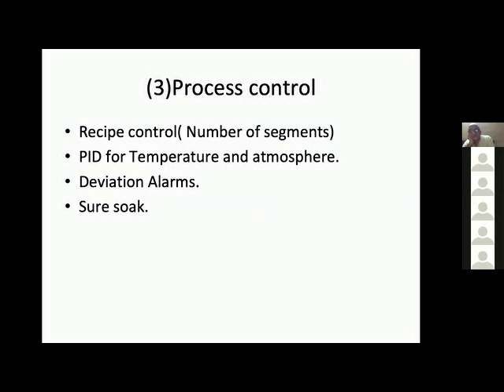The next is process control. Furnaces are equipped mostly with recipe control of the process. In some furnaces there is a limitation on the number of segments that can be programmed — like four segments: heating, carburizing, diffusion, and hardening. In other controllers you can program any number of segments. The advantage with more segments is that you can program ramp-up segments, which enables you to reach temperature and CP at the same time, making the process more repeatable. Otherwise, depending on the load, temperature may lag behind CP or CP may lag behind temperature.